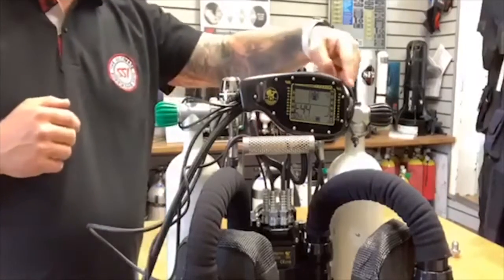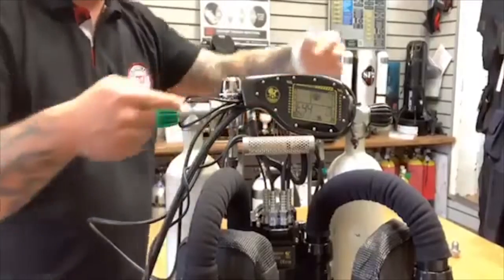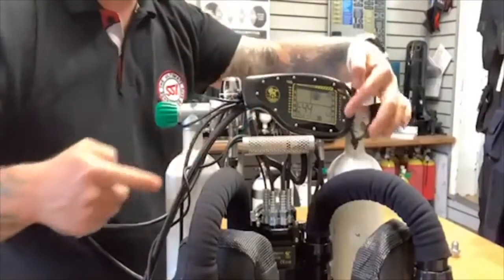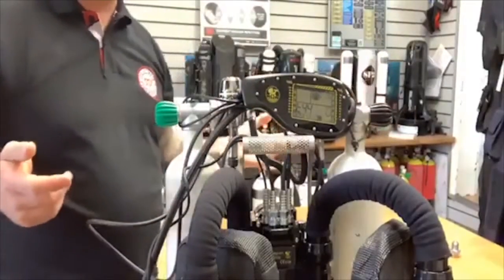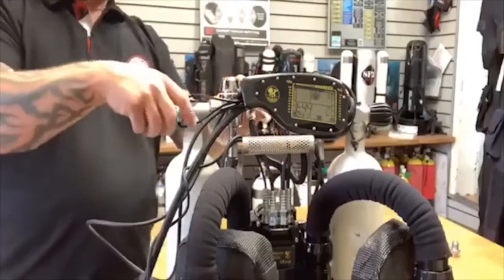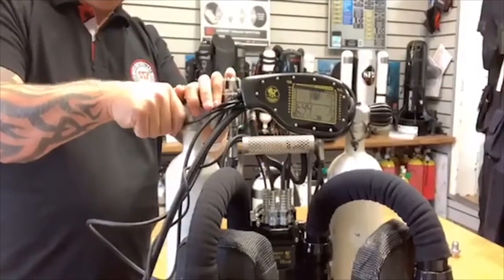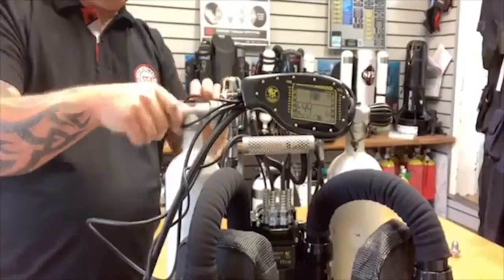Test 44, and you can see it on the screen, this machine is very intuitive. If it's flashing, that's what it wants you to do. So at the moment it's flashing oxygen down one side and diluent down the other side. So it's asking me to turn the gas on. I'm going to turn on the oxygen, again, nice and slowly, and you'll see the oxygen pressure will rise.